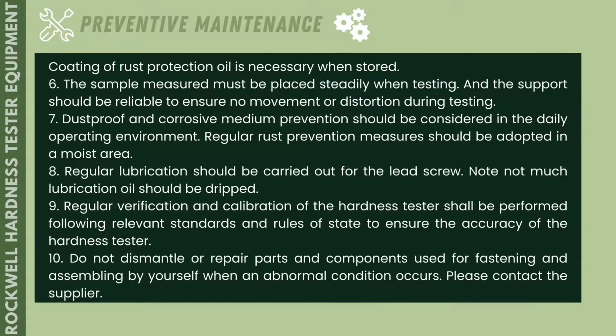Number 6. The sample measured must be placed steadily when testing. Then the support should be reliable to ensure no movement or distortion during testing. Number 7. Dust-proof and corrosive medium prevention should be considered in the daily operating environment. Regular rust prevention measures should be adopted in a moist area. Number 8. Regular lubrication should be carried out for the lead screw. Note, not too much lubrication oil should be dripped.